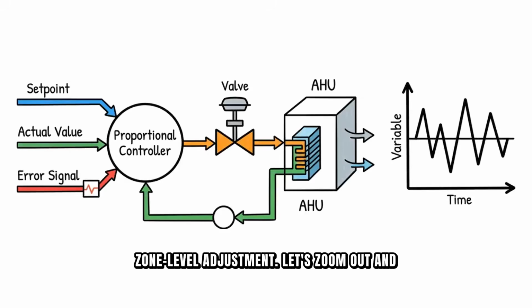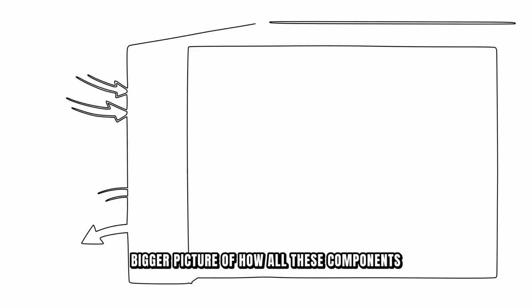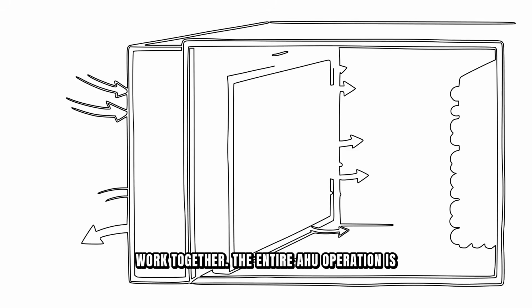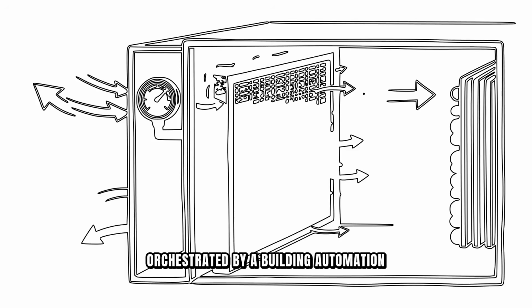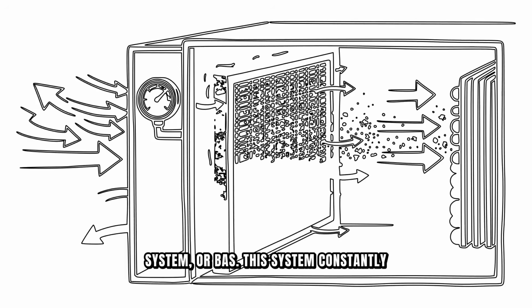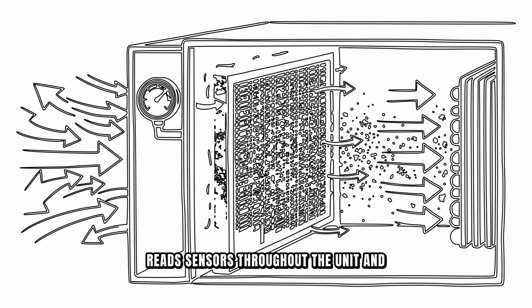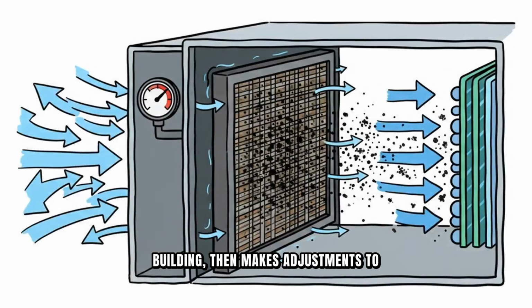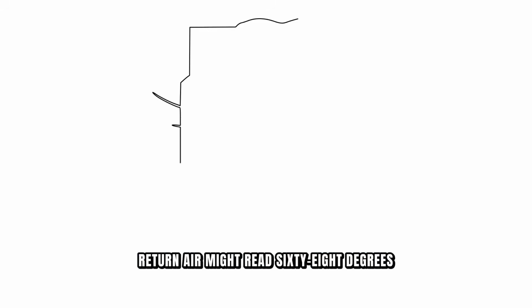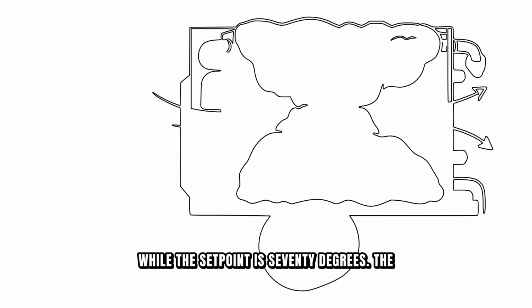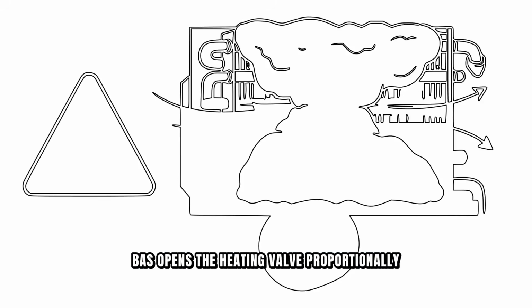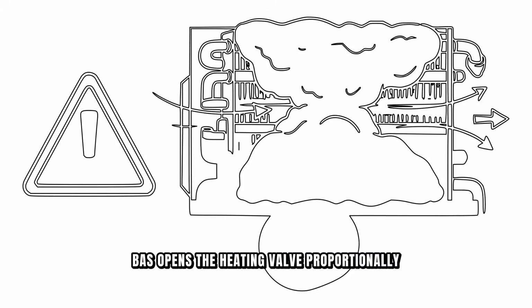Let's zoom out and talk about the bigger picture of how all these components work together. The entire AHU operation is orchestrated by a building automation system, or BAS. This system constantly reads sensors throughout the unit and building, then makes adjustments to achieve the set points you've programmed. For instance, a temperature sensor on the return air might read 68 degrees, while the set point is 70 degrees. The BAS opens the heating valve proportionally to get closer to that set point.